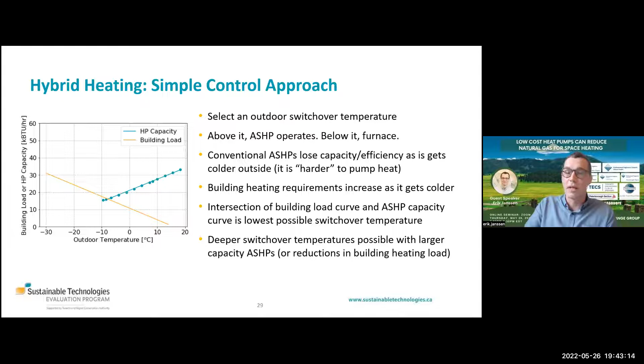But you can see that we can drive deeper switchover temperatures through two pathways. One, lowering the building load, maybe through building envelope upgrades that I mentioned earlier, or two, increasing the heat pump capacity. Both those things are going to shift that intersection to colder temperatures and allow us to do more of the annual heating load with our air source heat pump.